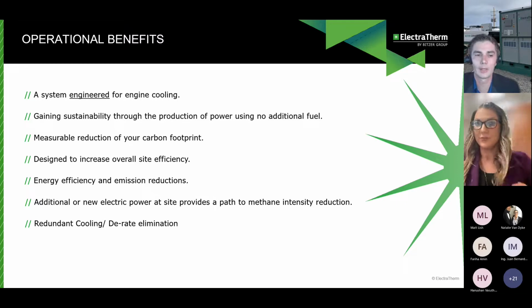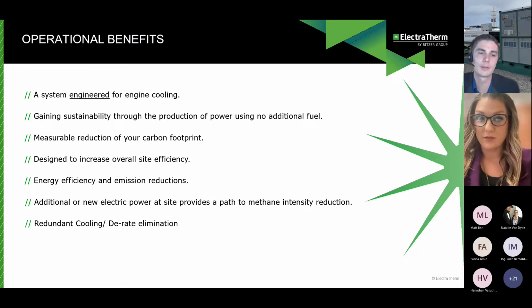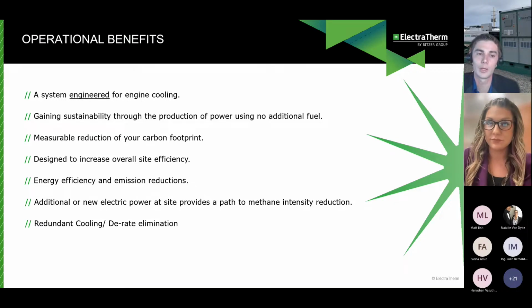With regards to derate elimination, as long as that derate is off of jacket water temperature, we can help eliminate it, and we can also cool the intercooler circuit, the low temperature circuit. The low temp circuit doesn't allow us to make power, but it is significant for cooling.